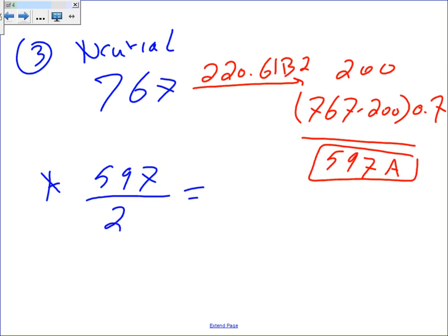Actually, I have no choice but to parallel two now, because I paralleled the hots, I have to parallel the neutral too. If I did the hots three, I have to put the neutral three. What's the answer? 299 amps.